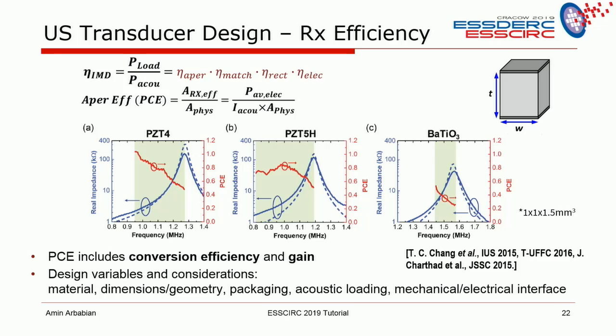Impedance—the dotted lines are simulations, and the solid traces are measurements. So when we characterize transducers, we think about aperture efficiency and their impedance profile across frequency. If we capture these two, we're able to model the transducer sufficiently well to build it into our system.